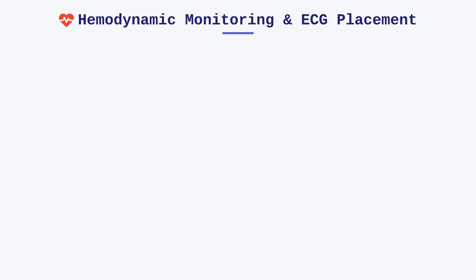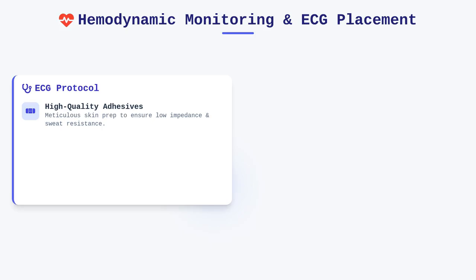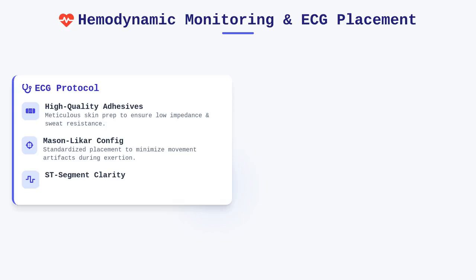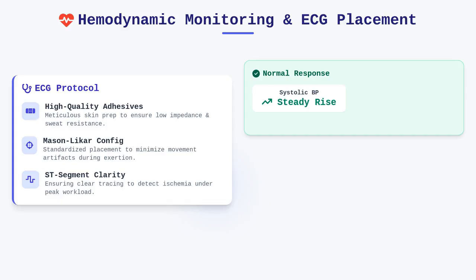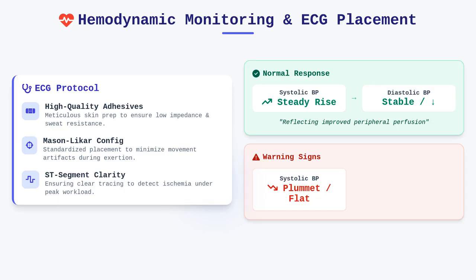Electrocardiogram placement and hemodynamic monitoring provide the safety net that allows us to push patients toward their physiological limits. A 12-lead electrocardiogram must be applied using high-quality adhesive electrodes, meticulously prepped to ensure low impedance despite the inevitability of sweat. Proper lead placement, following the standard Mason-Likar configuration, minimizes movement artifact that can obscure the ST segment during high-intensity exertion. Alongside the heart tracing, continuous blood pressure monitoring is essential to track the workload's effect on the systemic vascular system. A normal response should show a steady rise in systolic pressure with stable or slightly decreasing diastolic pressure, reflecting improved peripheral perfusion. Should systolic pressure plummet or fail to rise with increasing workload, this serves as an immediate warning of potential myocardial ischemia or impaired cardiac output.